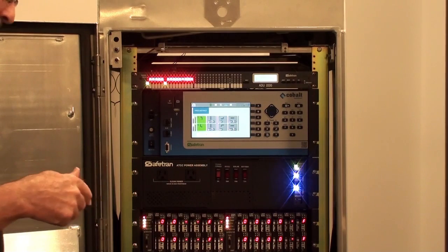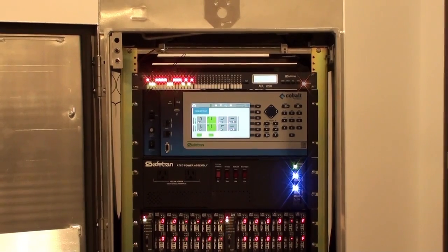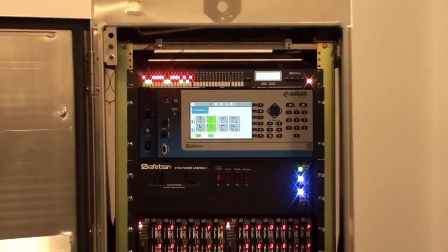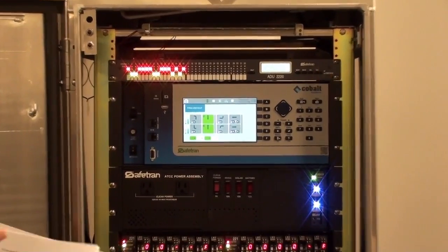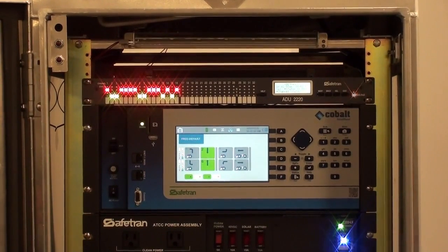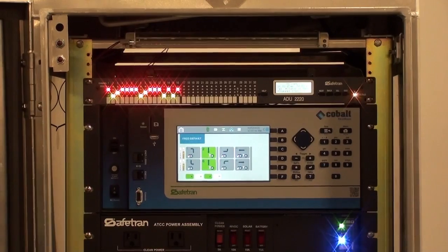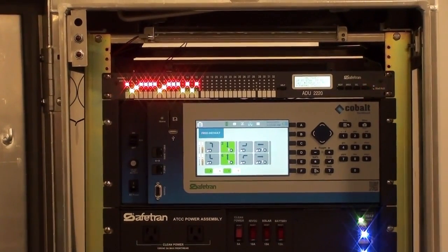A microcontroller in the power assembly reads the temperature sensor and determines when to activate the fans. It also monitors the current draw of the fans to help determine if the cabinet filter needs to be replaced or if the fans need servicing. The microcontroller can also adjust the cabinet lighting depending on the time of day. The fan lamp assembly can drive up to four LED lighting modules. All status is communicated back to the controller and can be relayed to the maintenance office.